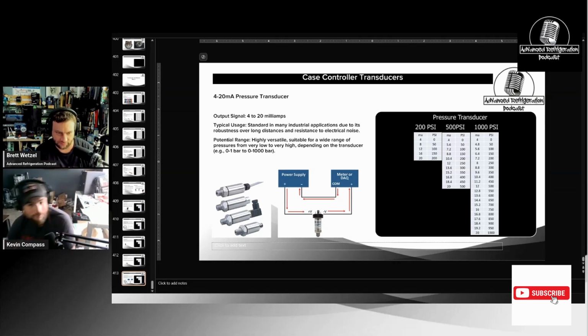I have not, because we don't do a lot of 4 to 20 milliamp work. I'm starting to get more into it because I'm starting to see it on other stuff, but that's going to give you your reading from the sensor. Now, as you're reading your milliamps, 4 milliamps is going to be 0 psi. If you have under 4 milliamps, you got a problem with the power supply, or you got a problem with the transducer. If it's reading under 4 milliamps, you're going to get an alarm for a bad transducer, bad open transducer, however that sensor is set up. If it's reading over 20 milliamps, it's going to read an alarm for that. On that scaling, like how he has it on there, 0 to 200, at 4 milliamps is 0. At 20 milliamps, it's going to be 200 psi.